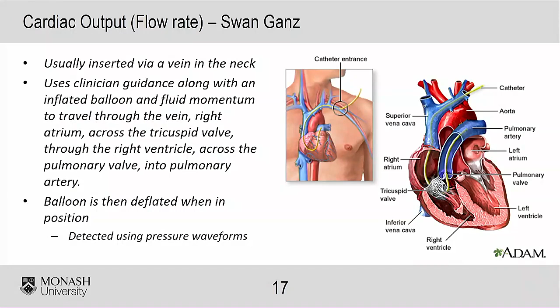This is essentially the way it works. So once it's in the pulmonary artery, the clinician injects a bolus, or essentially a volume of fluid, cold saline in this case, into the catheter. So it has a hole that goes all the way through it that can carry that fluid. So the clinician from outside the body injects the cold saline through that port. That cold saline comes out in the right atrium, in here, and then it travels through into up here, where we have a temperature sensor on it, and then we can use the time essentially that it takes for the cold to come through here and be measured as a way to calculate cardiac output.